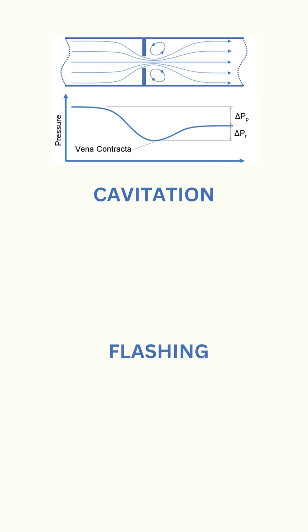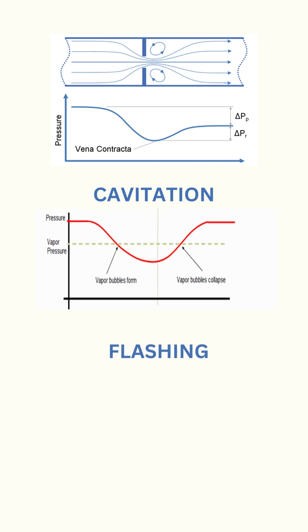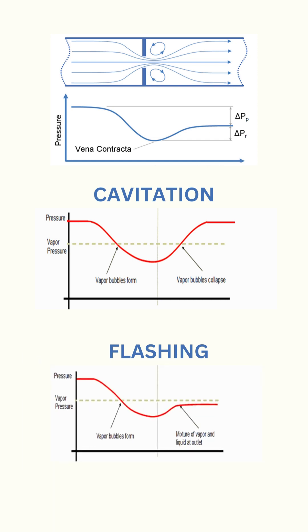As the pressure increases again, if this pressure is greater than the fluid vapor pressure, cavitation shall occur. If it is less than the fluid vapor pressure, flashing shall occur.